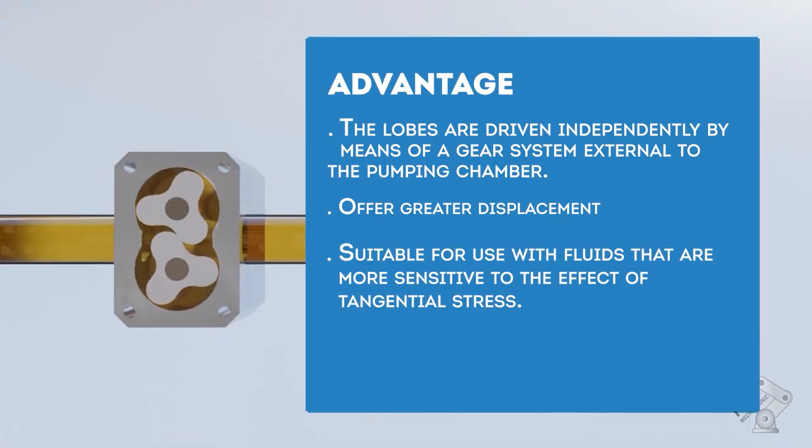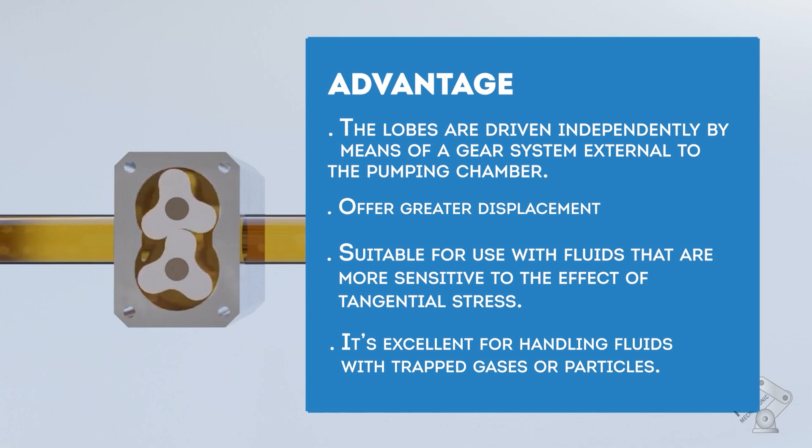Advantages of this type of pumps. The lobes are driven independently by means of a gear system external to the pumping chamber. They offer greater displacement, but their cost is higher than other types of pumps. This pump is suitable for use with fluids that are more sensitive to the effect of tangential stress or shear. Excellent for handling fluids with trapped gases or particles.